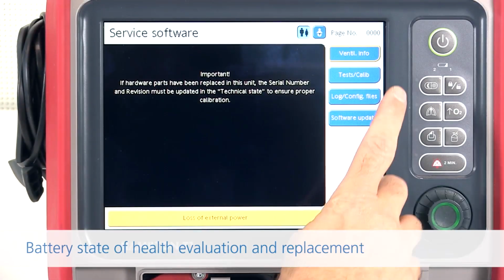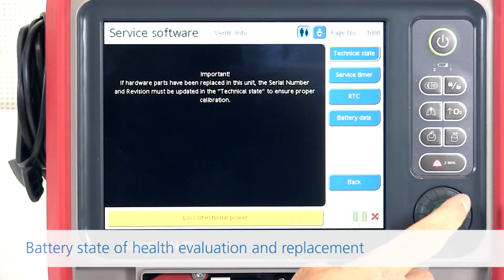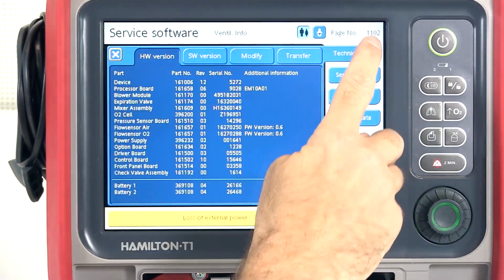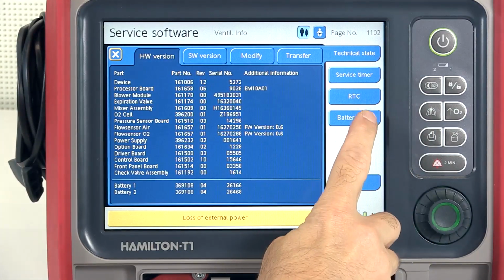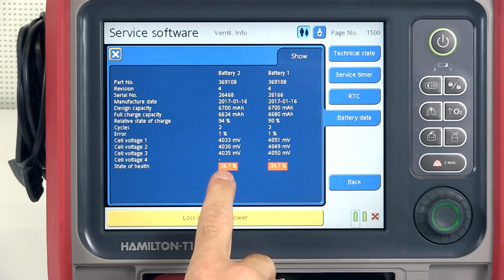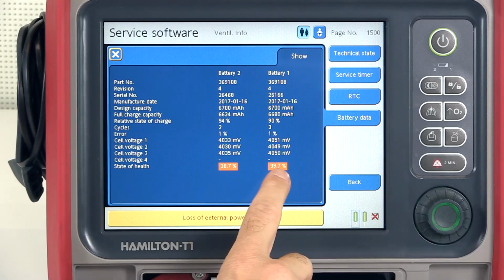In the main service software screen, touch Ventilator Info, Technical State, and then Battery Data. Consider replacing the batteries when the state of health shows a value between 20 and 40%. The batteries must be replaced once the state of health is less than 20%. Here, the two batteries show a state of health just below 40%.